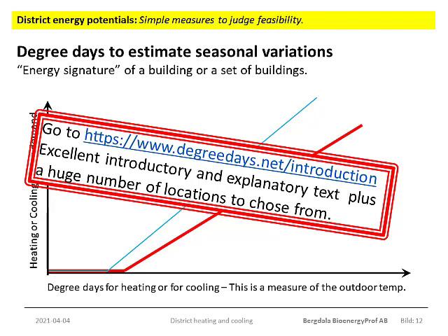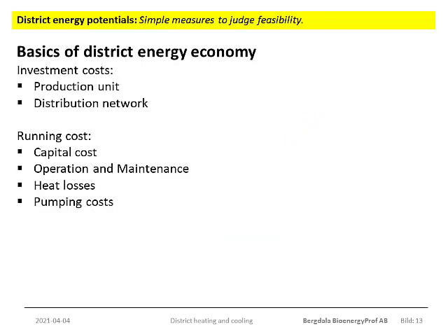Since data can be aggregated for days, weeks or months, it will also be simple to aggregate the degree days so as to match the bills from the energy company. Thus you can set up the energy signature for an existing building, only provided you can see the energy bills. Only if, in the future, you need access to more advanced tools for analysis will you have to pay for it. We will not spend much time on economy, but a few things need to be mentioned.